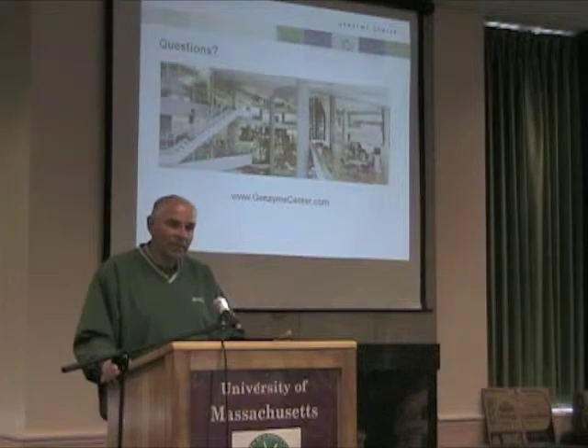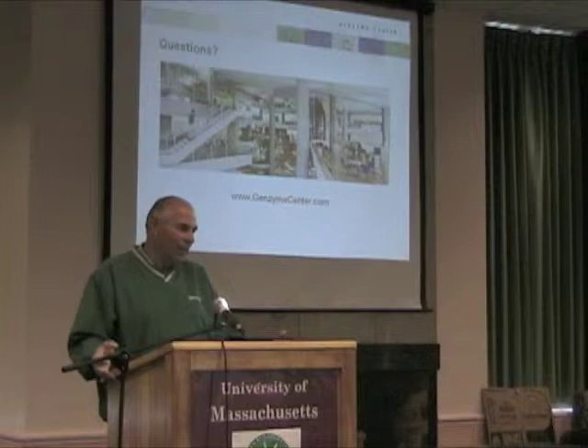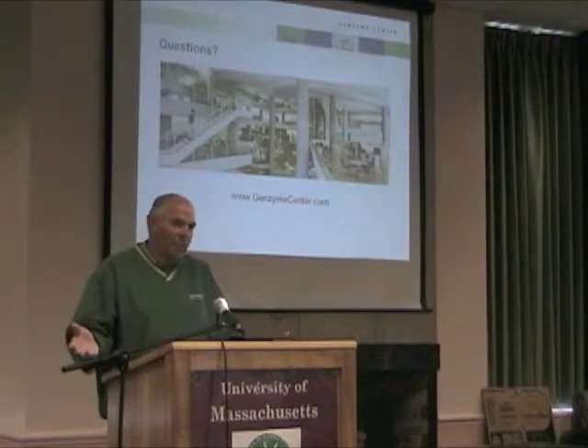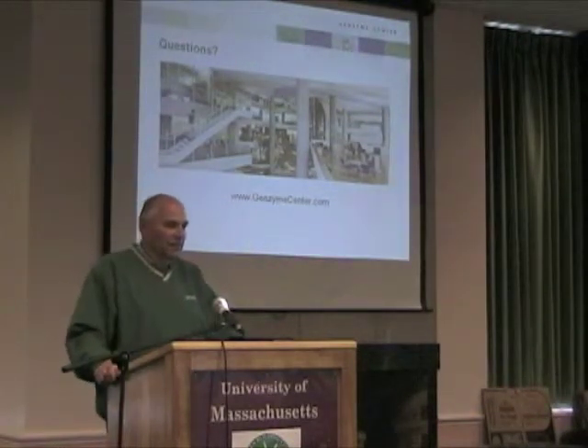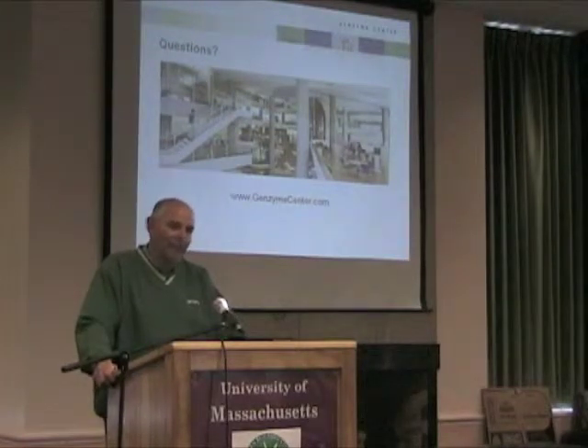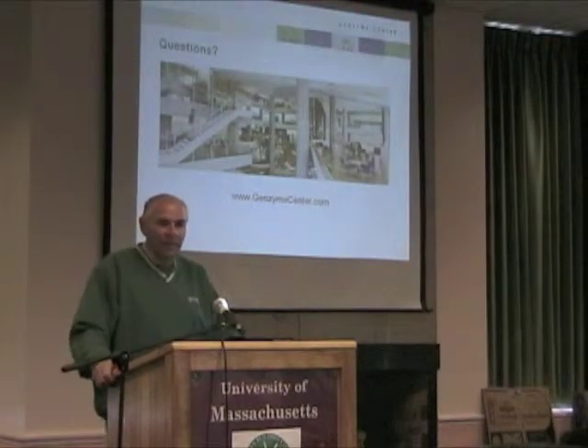Changing the light sequences, shutting down the air handlers more than we did before. The fan coils are going off, they're not on as long. A lot of the lights, there's no reason why we have the lights on at 6 o'clock in the morning till 9 o'clock at night. People at Genzyme don't show up at 10, they leave at 4. So we cut back on that. I hope that answers your question. I do have a lot of numbers for you if you'd like them. I can show you percentage-wise what we used at the beginning compared to now. We've cut our steam cost down more than half. And because of that, that extra chiller.